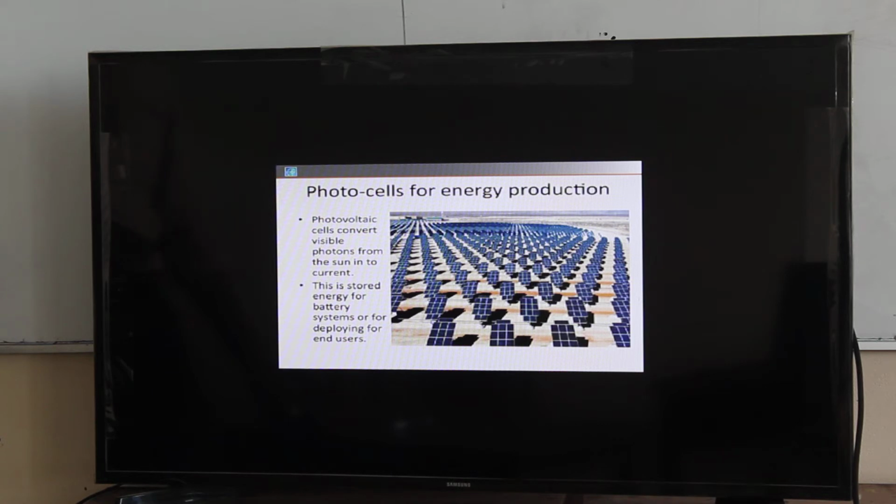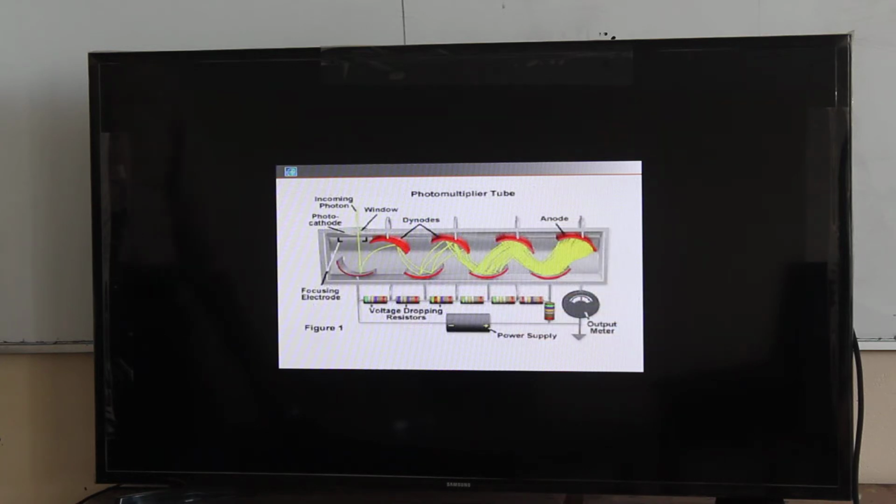of light. A photomultiplier tube is essentially an evacuated small cylinder where a photon comes in through a window, shown here on the left-hand side, and hits a small piece of metal, which is at a voltage. When the photon hits the window, it is sometimes coated with a material that has a very low work function associated with it.